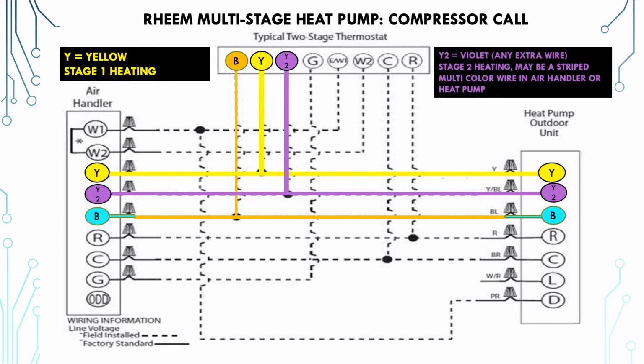Now, with your yellow wires, at this point we are going to talk about stage 1 and stage 2. Your yellow wire is going to be on the Y contact, and it's going to be utilized for wiring up stage 1 and stage 2. Now, it should be labeled as Y1 or Y and Y2 on Rheem equipment. Some will say Y and Y1 and then Y2. So you just have to pay attention to how that particular model or brand is deciding to label the various stages of the equipment. However, you have to have enough wires for the multi-staging.